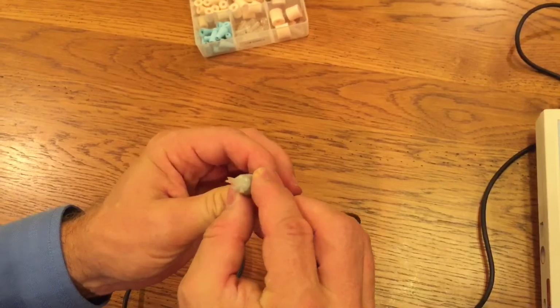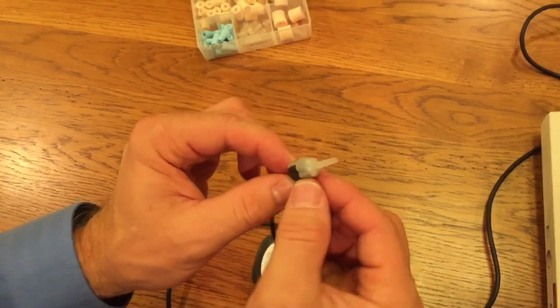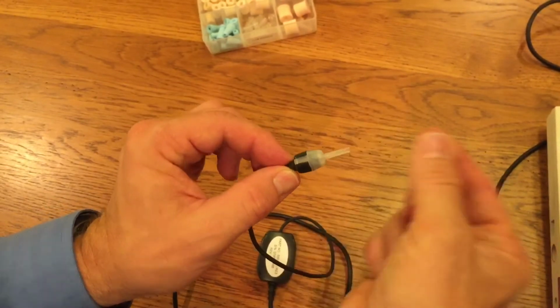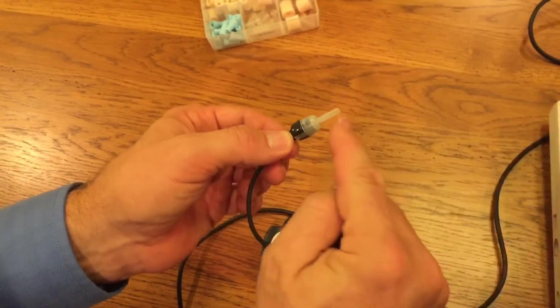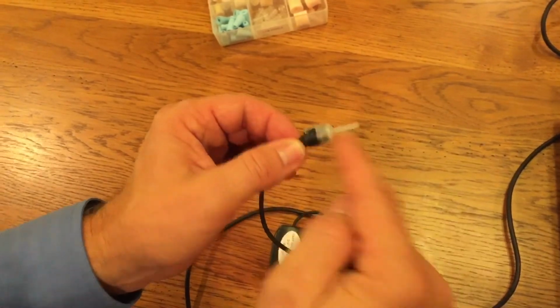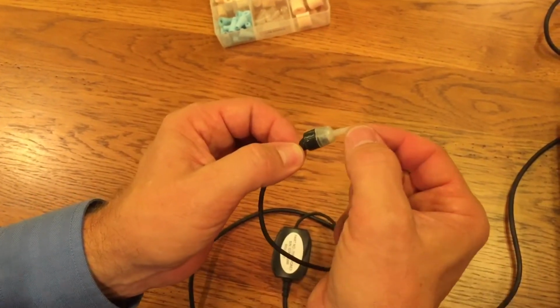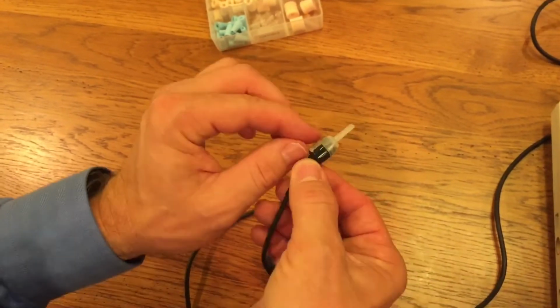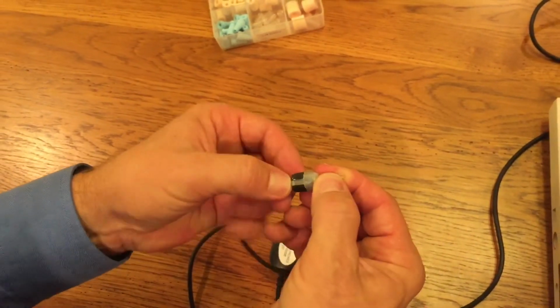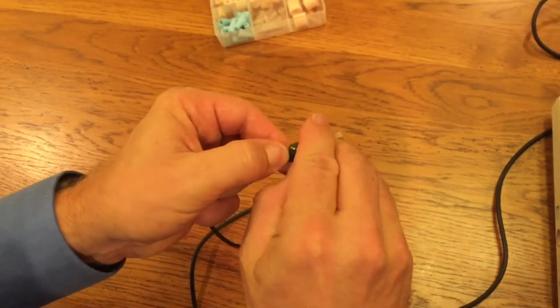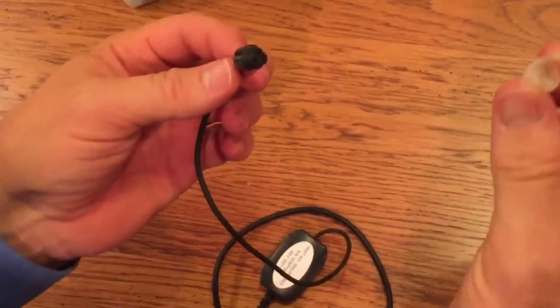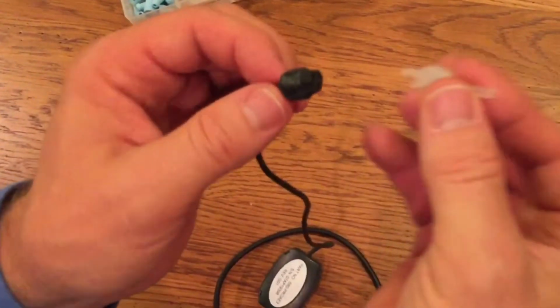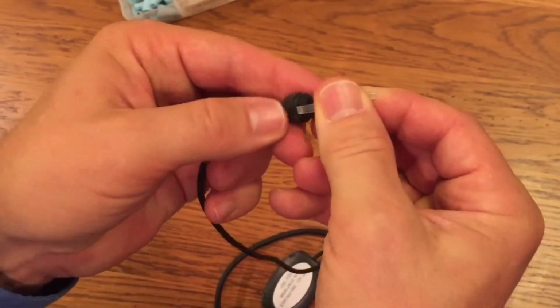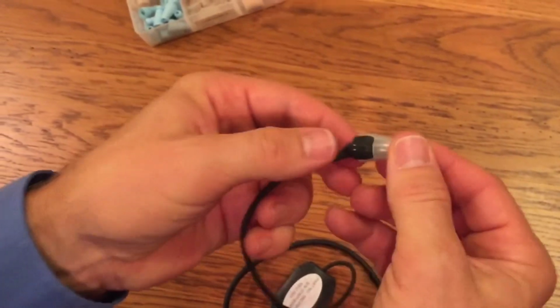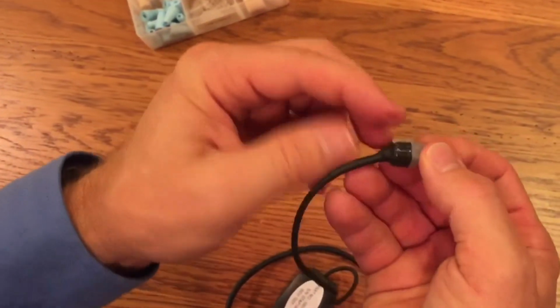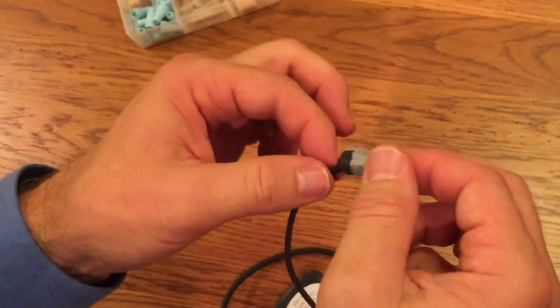Now you want to look at the probe and make sure that it is clean. There's no earwax. If we need to clean it, we will clean it by pulling away from the probe tip so we don't get moisture or cleaning materials inside the probe. If this probe nozzle becomes clogged, you would unclip it from the sides and pull it off. Discard the old nozzle and then replace a new one on it, by just spreading it over the grooves and pushing it all the way to the base, and make sure the ends are clipped in.